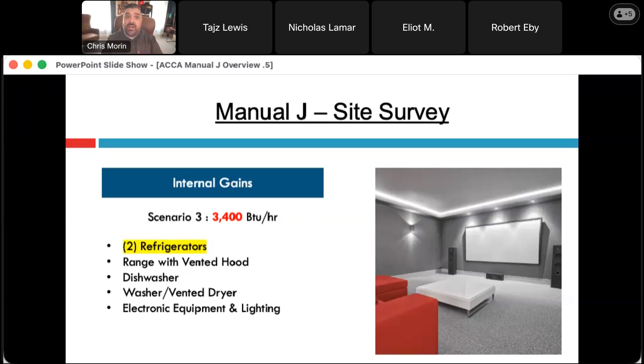Scenario number 2 for a block load includes a dishwasher, a washer, a vented dryer, and standard electronic equipment and lighting that's on during peak demand, right? 4 or 5 p.m. And that's 2400 BTUs. However, most new construction homes have an additional refrigerator or a freezer on top of that, and or a wine cooler that's fairly large, always putting off some heat. So therefore, scenario number 3 is probably more likely what you would see in a lot of new construction, larger square footage homes. Typically in Austin, I believe the building code looks for somewhere around 3,000 BTUs per hour or less on internal gains. But if you have a reason to add, make sure you add to those spaces.